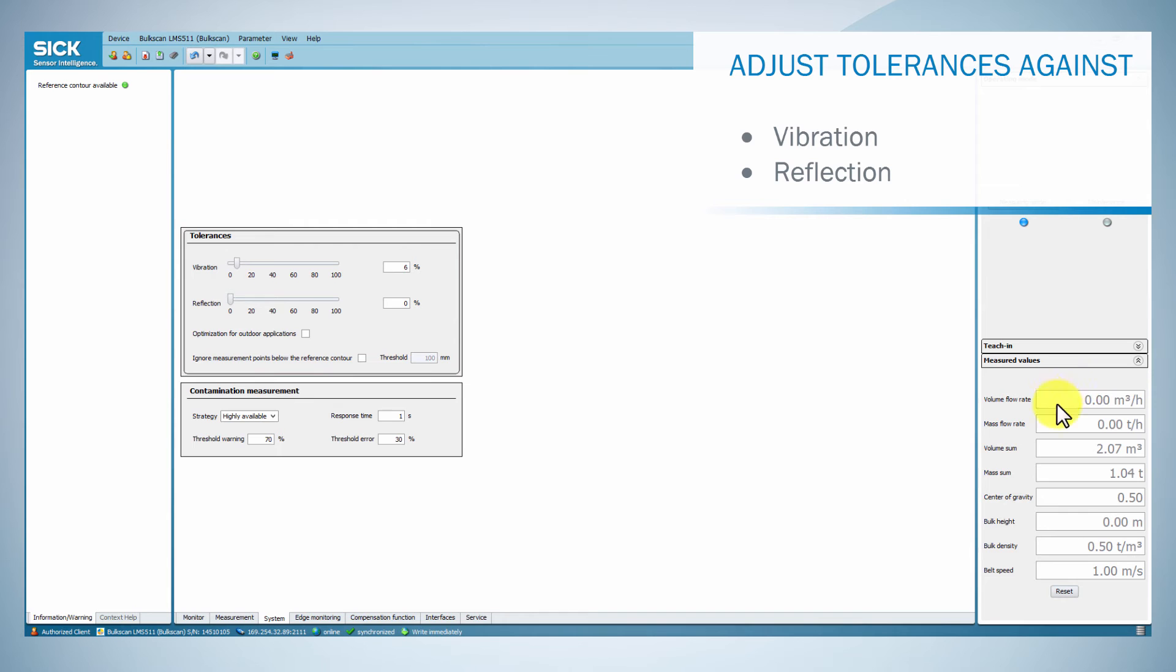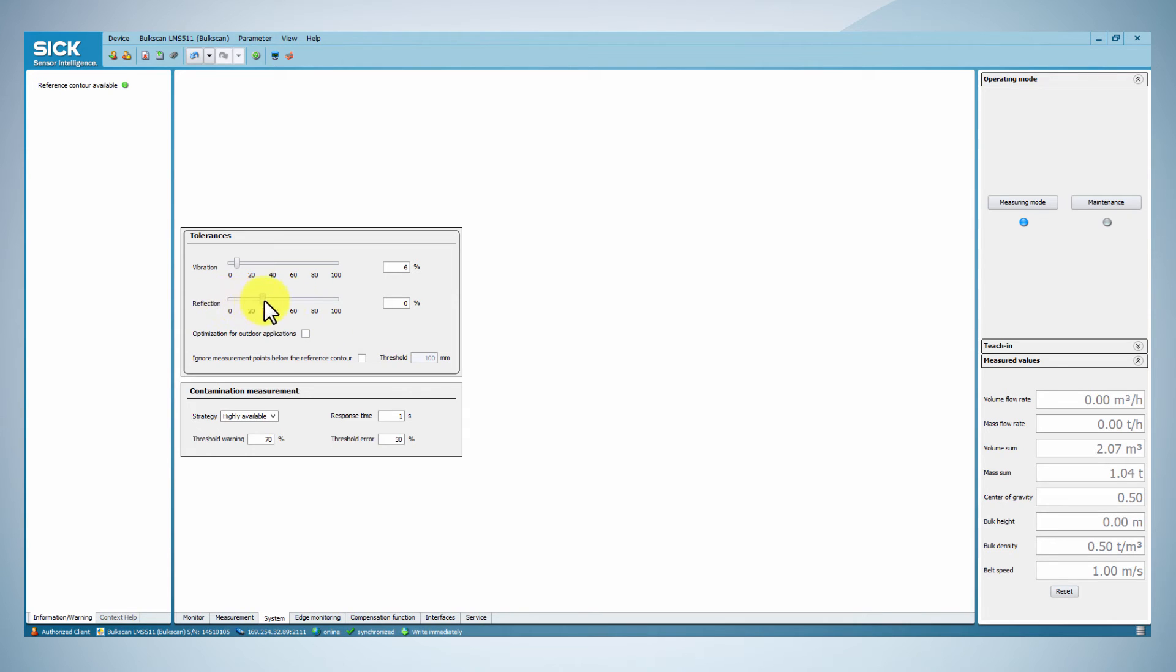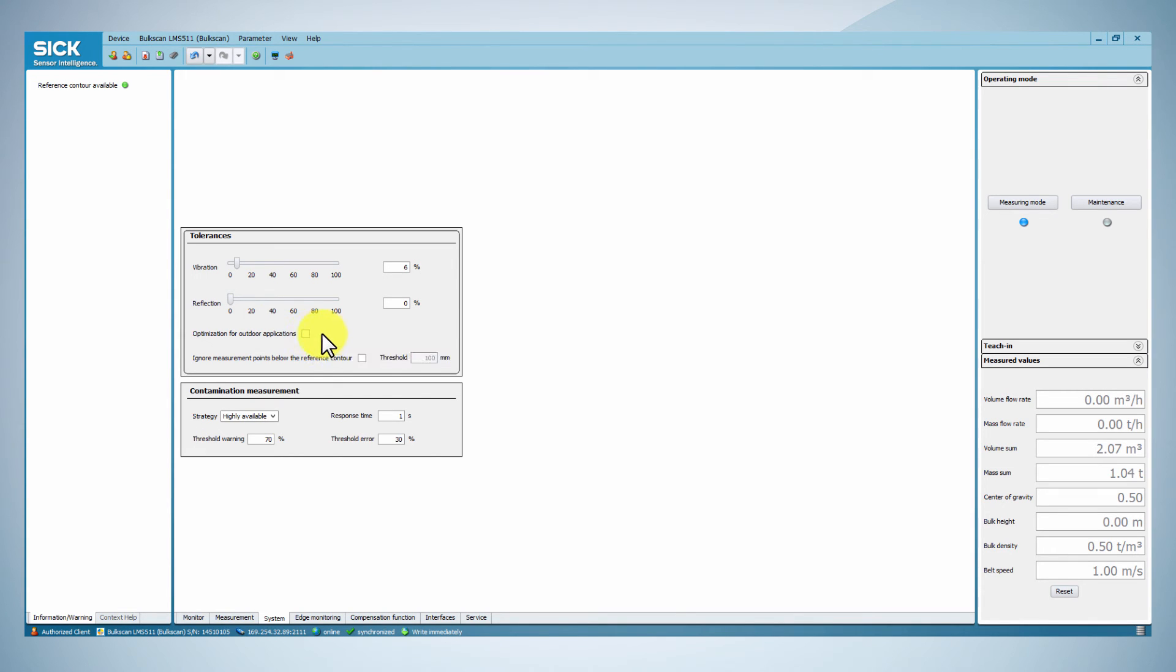Reduce or increase the tolerance against vibration so that the volume flow rate measured value remains constant at zero, with an empty conveyor belt. Reduce or increase the tolerance against reflection so that the reliability of the system meets your requirements.